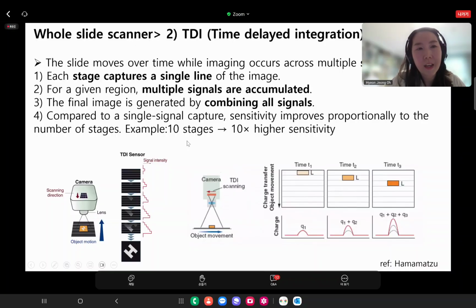And the upgraded version of line scanning is TDI scanning. In TDI scanning, the slide moves over time while imaging occurs across multiple stages. Each stage captures a single line of the image. So for a given region, multiple signals are accumulated, and the final image is generated by combining all signals. Compared to a single signal capture, sensitivity improves proportionally to the number of stages.